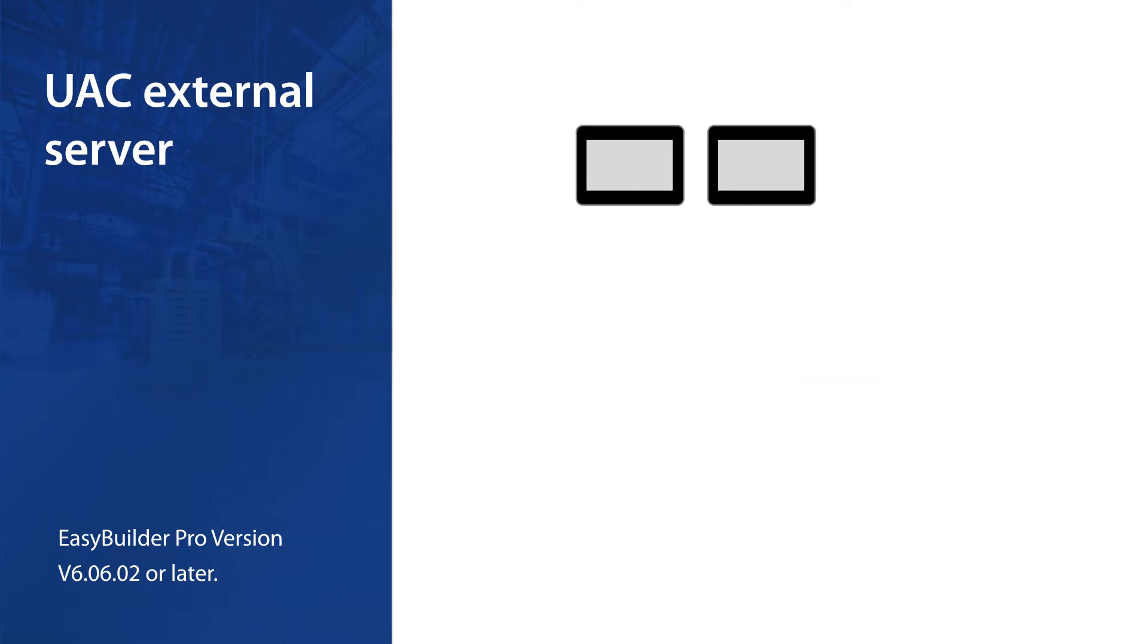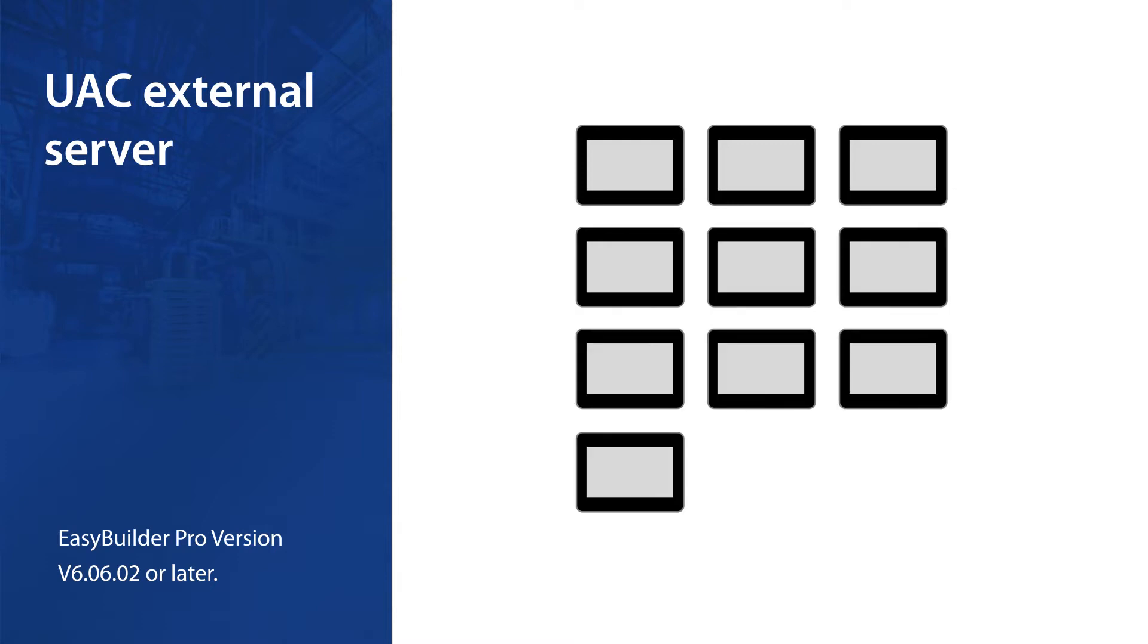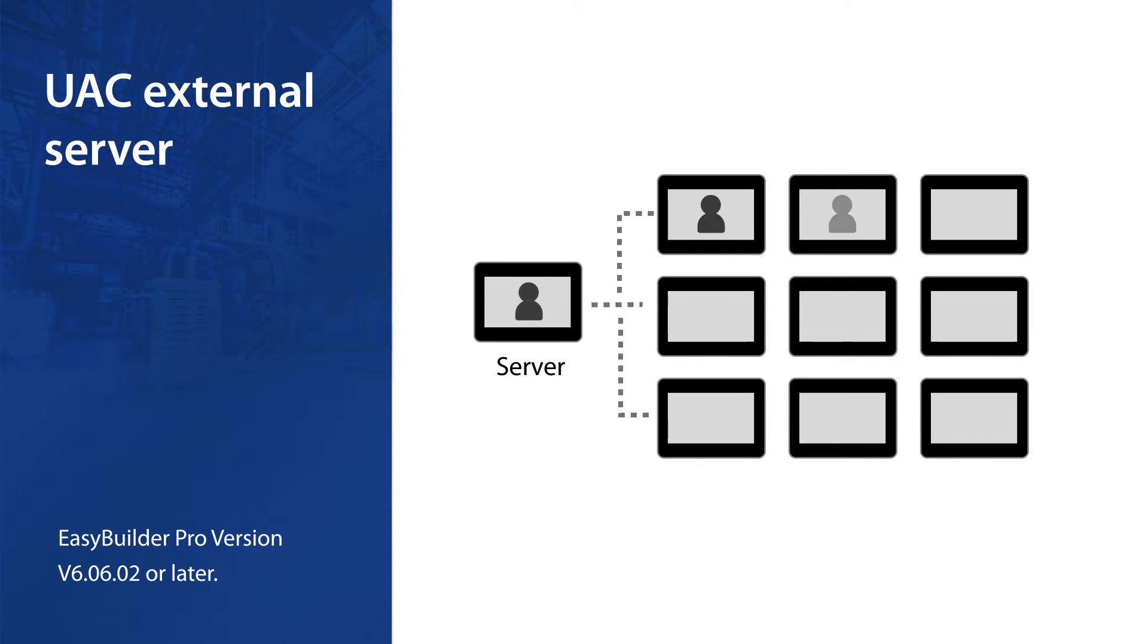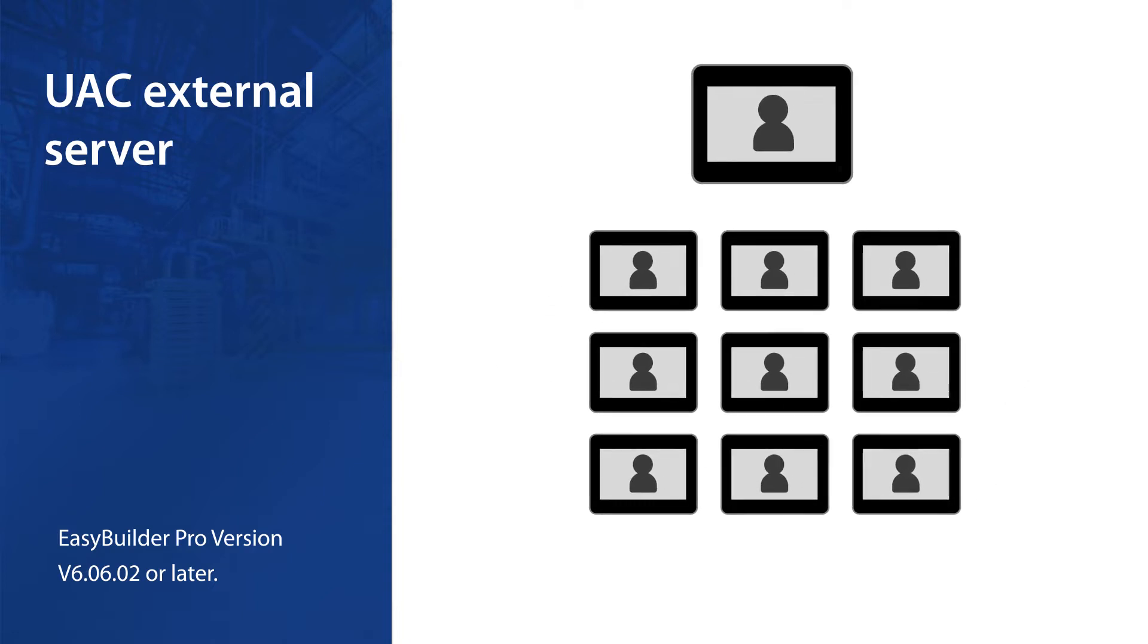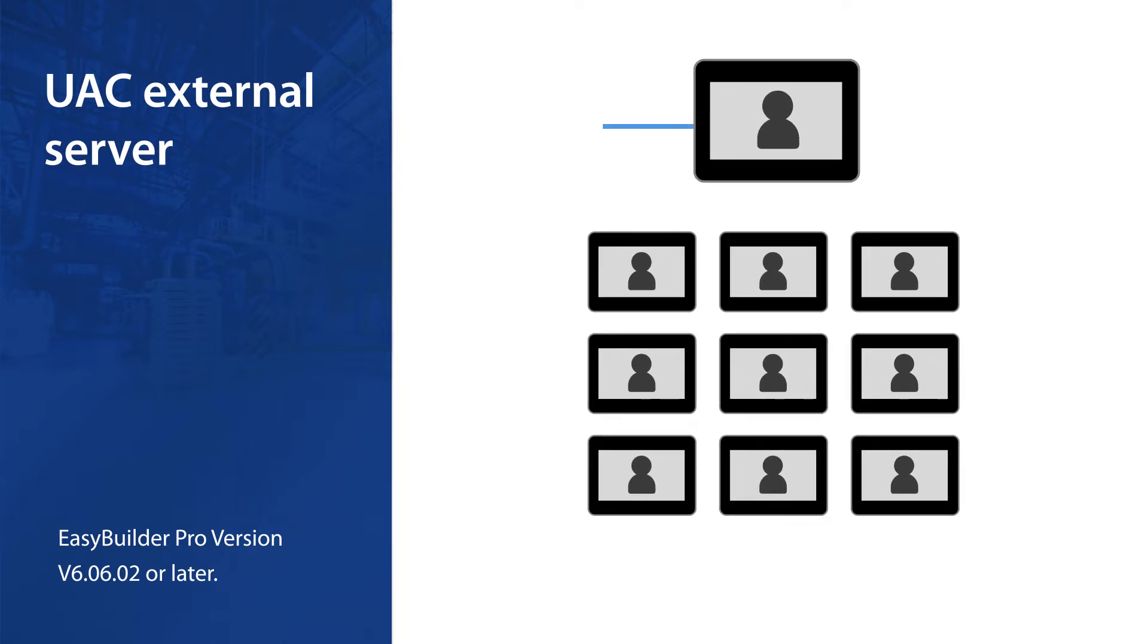In this tutorial I will show you how to log in with remote HMI accounts. Suppose you have 10 HMIs in your application, you can just use one HMI to be the central user management server and have the other nine HMIs use the same accounts to log in. So you don't need to manage the users on every HMI.